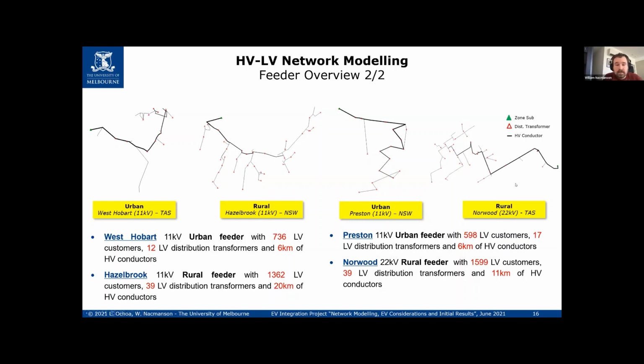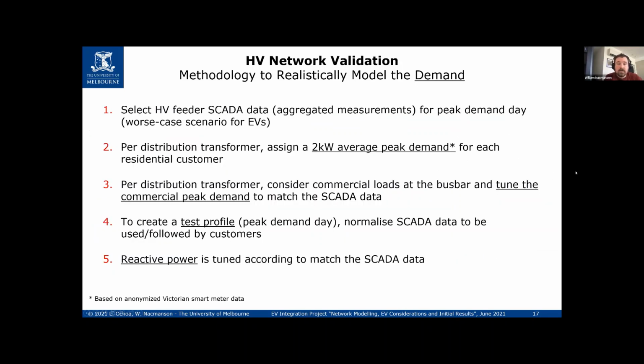Thank you. So if we move to the next slide please - how do we go about making sure our models are sensible? How do we translate this all into OpenDSS? First, we look at our data. We select our HV feeder, whatever one we're looking at, and look at the measurements provided - power, reactive power, apparent power, current, voltage, all at the head of the feeder.